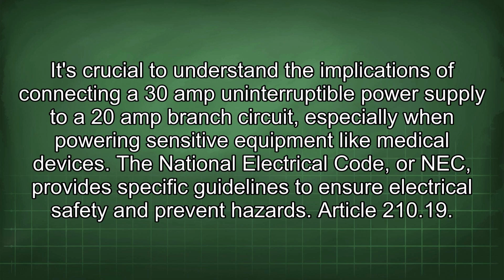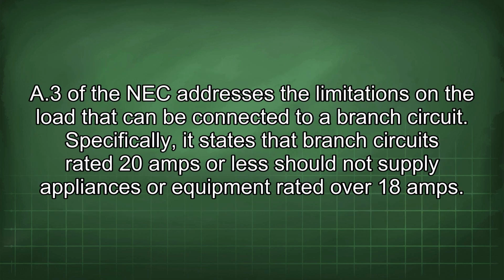It's crucial to understand the implications of connecting a 30 amp uninterruptible power supply to a 20 amp branch circuit, especially when powering sensitive equipment like medical devices. The National Electrical Code, or NEC, provides specific guidelines to ensure electrical safety and prevent hazards. Article 210.19(A)(3) of the NEC addresses the limitations on the load that can be connected to a branch circuit.